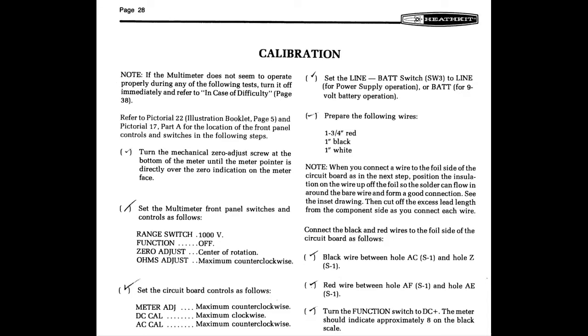Okay, we turn the mechanical zero adjust screw at the bottom of the meter until the meter pointer is directly over the zero indication of the meter face, and we've done that. Set the multimeter front panel switches and controls as follows. Range switch on 1000 volt, we did that. Function to off, we did that. Zero adjust, center of rotation, we did that. Ohms adjust, maximum counterclockwise. And I don't think I did that. I think I put them both in the center of rotation.